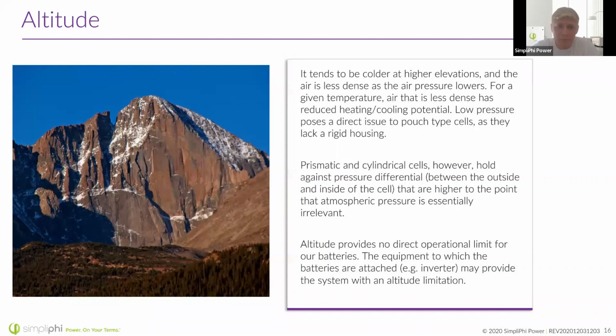For our batteries, the main concern at high elevations is actually temperature, because the air at high altitudes is less dense, and has reduced heating and cooling potential. High elevations are often the same places you find very low temperatures, and that reduced heating and cooling potential combined with low temperature is what can cause issues. So even with the altitude question, I'm always pointing back to temperature as the real thing to be concerned about.